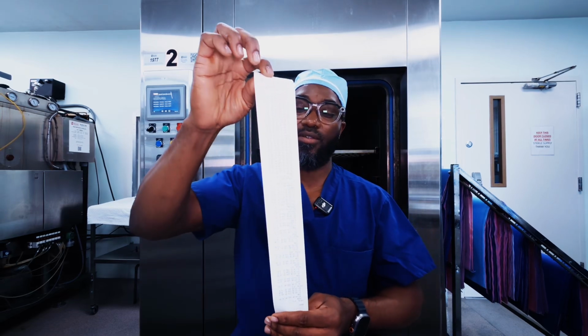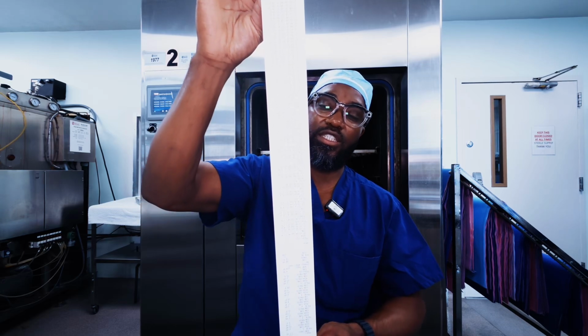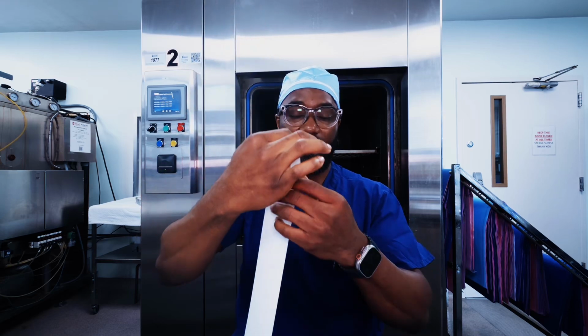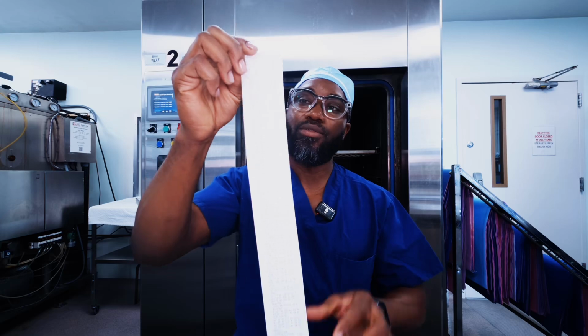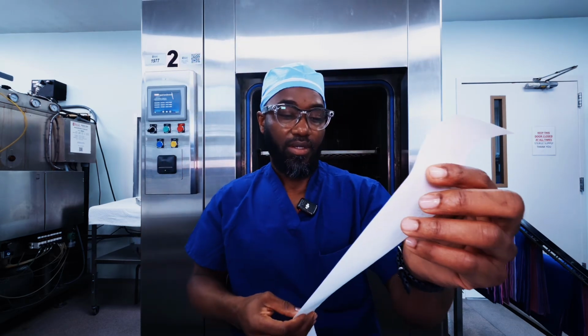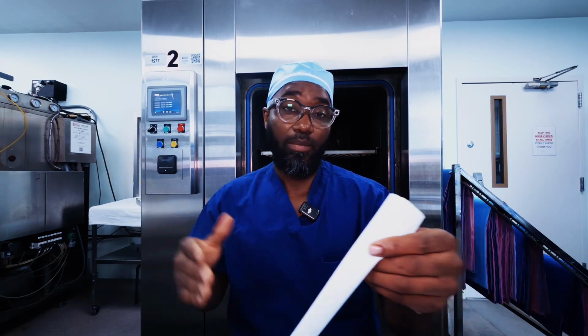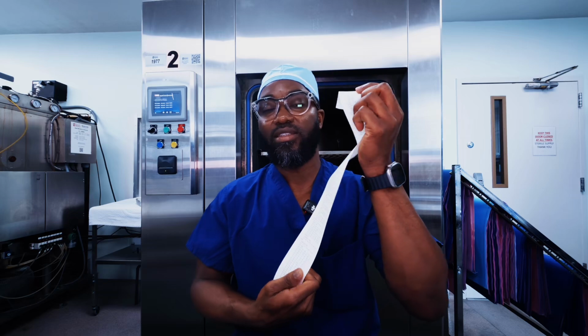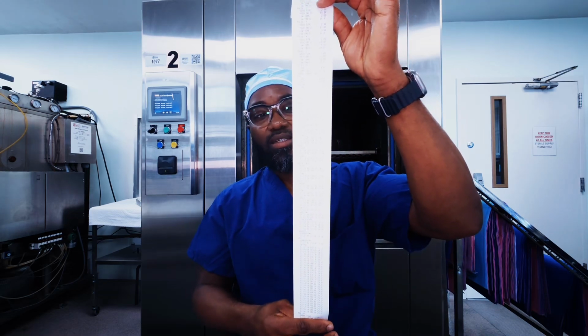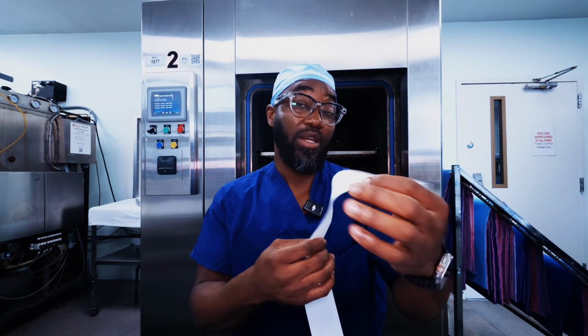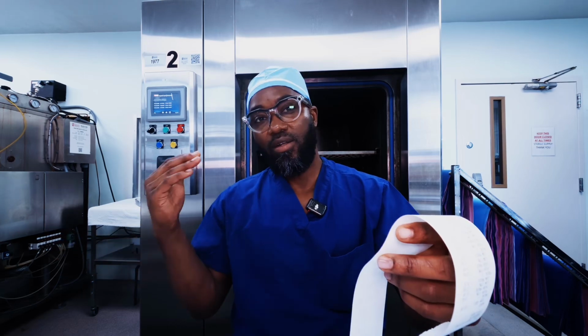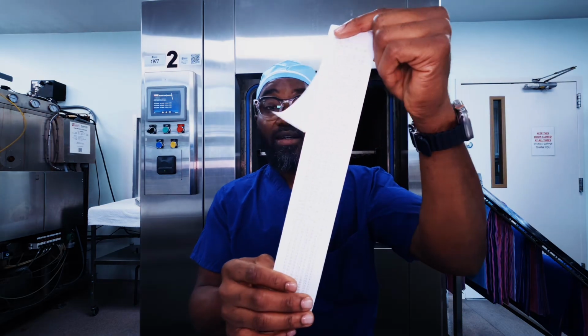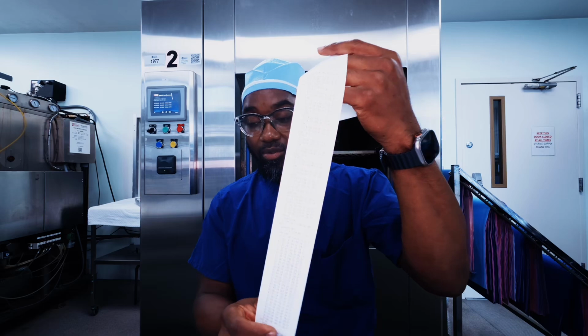Your third examination will be a physical printout. During your sterilization cycle, your machine prints out a detailed graph of the process of the sterilization cycle. On this graph, it tells you the exposure time or the parameters that your instrument should be exposed to based on what the manufacturer says. Usually the manufacturer gives you an instruction on how to sterilize the instrument. For example, the instruments that we sterilize require us to sterilize for a minimum of 4 minutes at a minimum temperature of 270 degrees Fahrenheit. Based on the manufacturer instructions, we now have to physically verify that we met all of the required parameters.